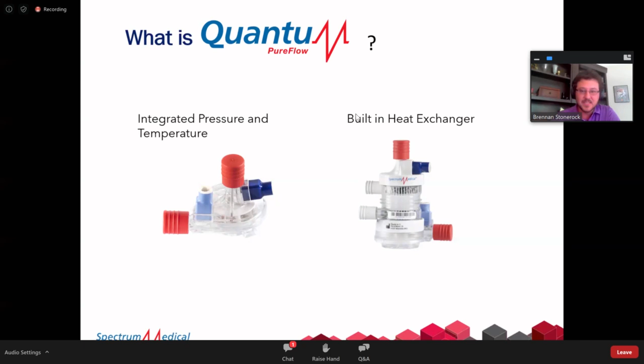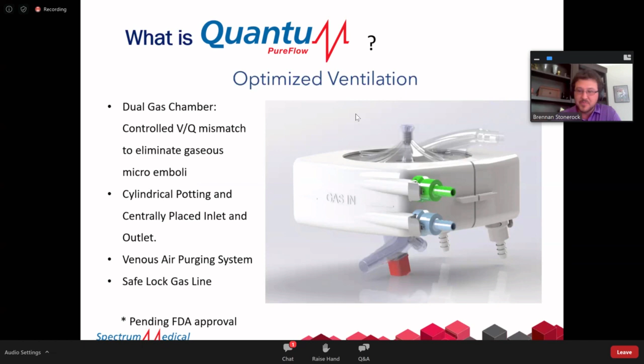So moving on into disposables, we are working on this and submitting to the FDA. This is our oxygenator or ventilator. And same like with the centrifugal pump, we had specific design considerations. Number one being the issue of clotting. So by creating a cylindrically shaped membrane and mimicking the shape of a blood vessel, we can reduce stagnant areas, platelet activation, and hopefully increase efficiency. Next, we centrally place the inlet and outlet, which allows for improved velocity and flow. This reduces the turbulence and stagnation, which leads to less clot formation.